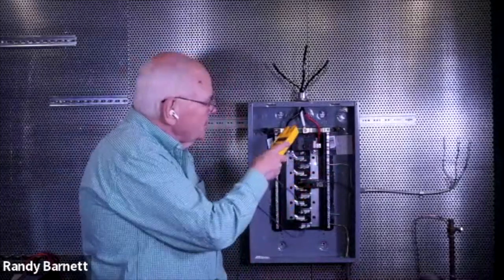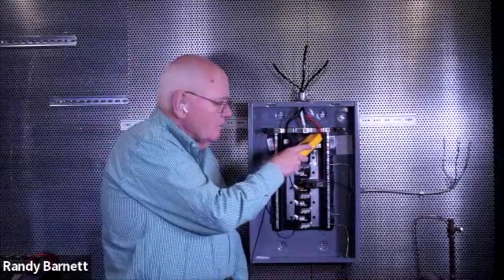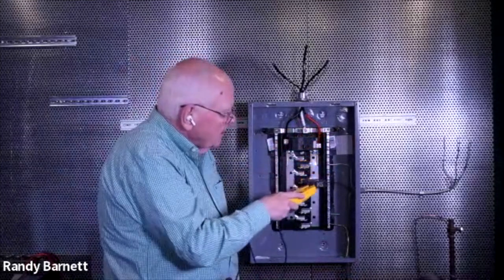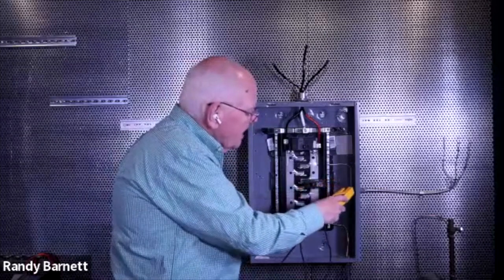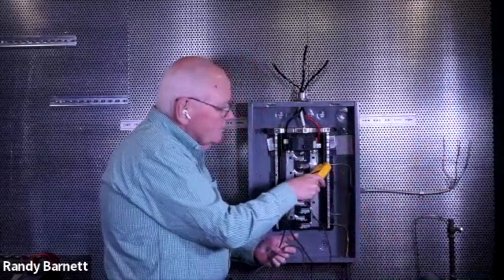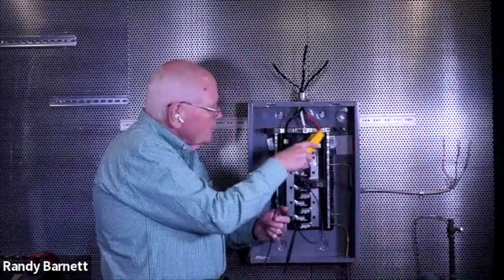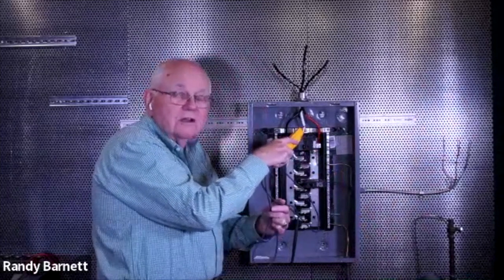So current would flow in, in this case, on the red wire, wouldn't it? Come on down through the bus bar, go out the circuit breaker, and go out on the black wire. And current would flow out here along the black wire into the load. And then current wants to go back to the source, so it could return back to the source through the neutral wire, the white neutral wire, and of course return on back to the neutral bus bar. And then the neutral bus bar is attached to the neutral on the transformer, so it has that complete path of current flow, right? So that's good. Current's happy. It gets to where it wants to go, okay? Which is always back to the source.